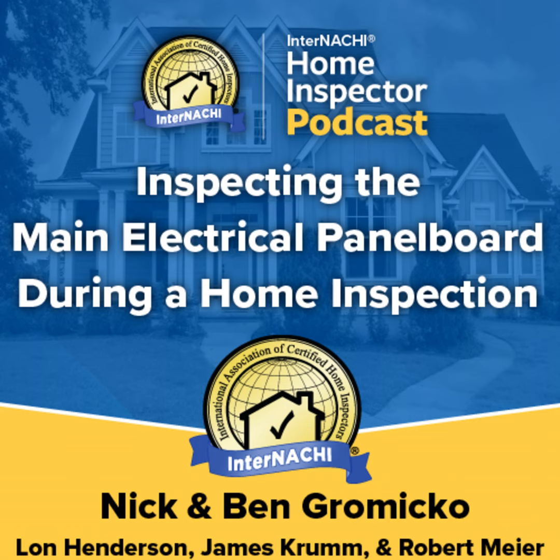There is usually an indicator LED light that indicates the proper function of the surge protector. Most surge protectors are sacrificial or single-use devices. If there is a large power surge, the surge protector dies, protecting the system, and must be replaced. If the LED is not glowing, typically green, then the surge protector should be reported as needing replacement.